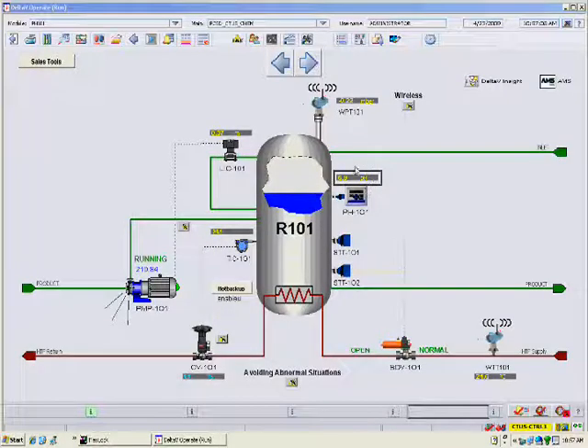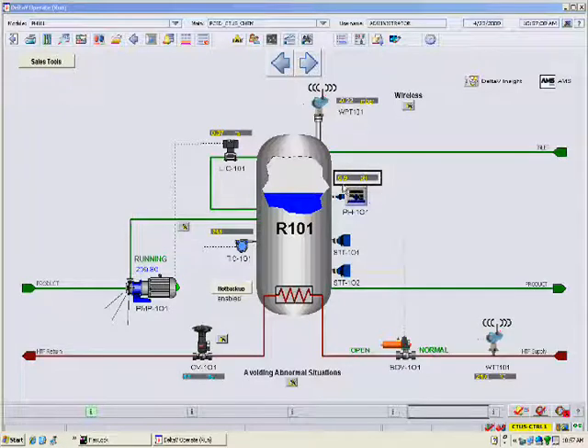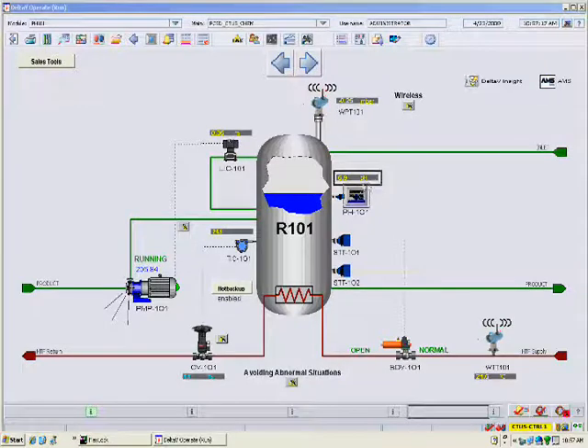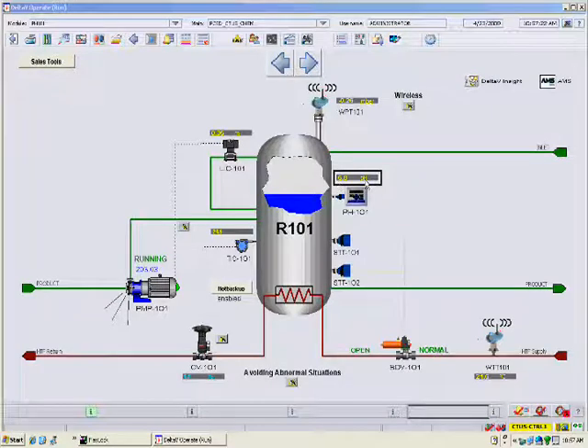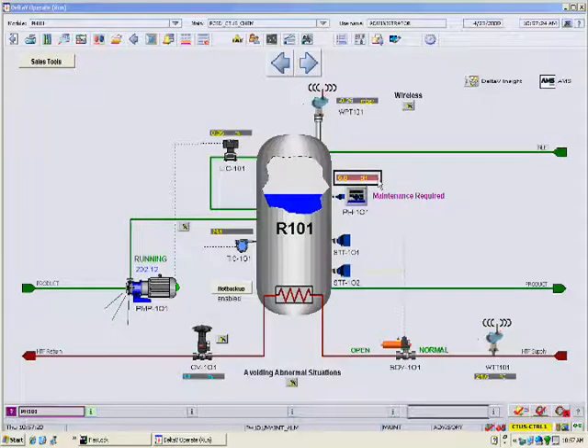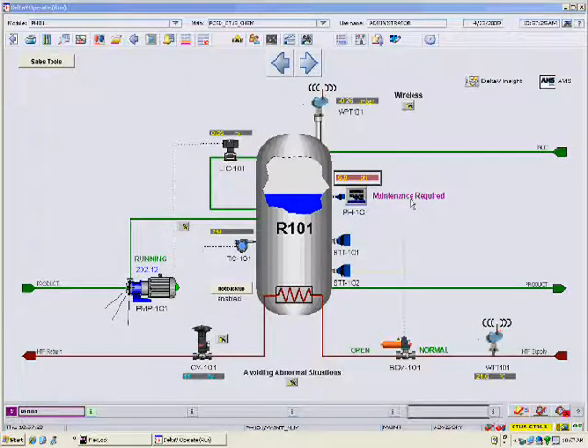Let's first look at a Foundation Fieldbus PH Transmitter. This is the operator console display in normal operation. There are no alarms in the alarm banner at the bottom of the screen. The control system captures diagnostic alerts from fieldbus devices in the system. When a device failure is detected by device self-diagnostics and reported across the fieldbus, it automatically appears as a device alert in the alarm banner at the bottom of the screen.